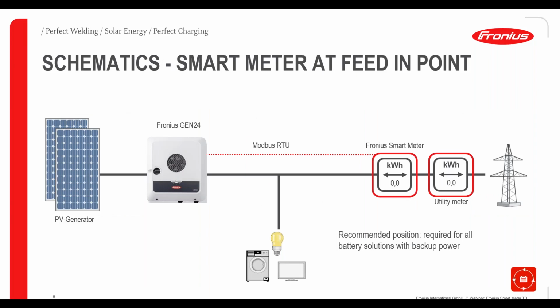Moving forward, there are 3 different ways of installing a smart meter in a PV system. The first option is to install it in the feeding point of the system, which is the recommended position. It's not mandatory, but as said, it's recommended. But if we have a battery in the system, for example a backup system, then it's mandatory to have the smart meter in the feeding point, of course. Then we know the exact surplus energy being fed to the grid, and together with the communication of the smart meter to the inverter, the inverter knows that surplus energy can be charged to the battery instead.